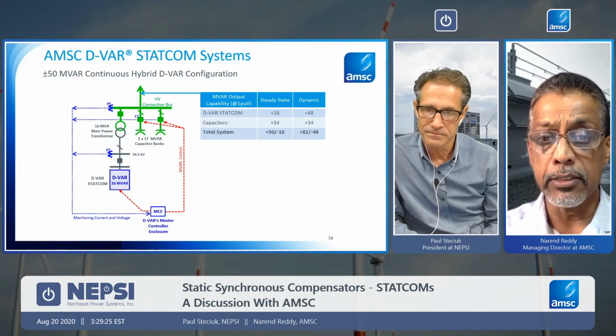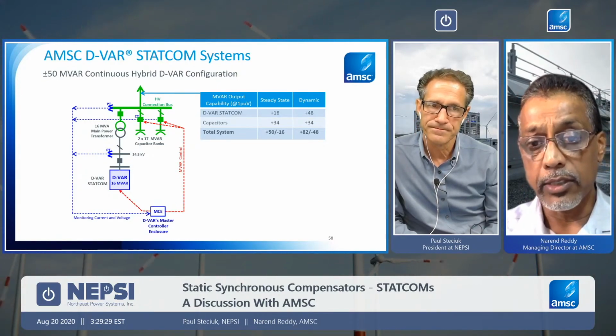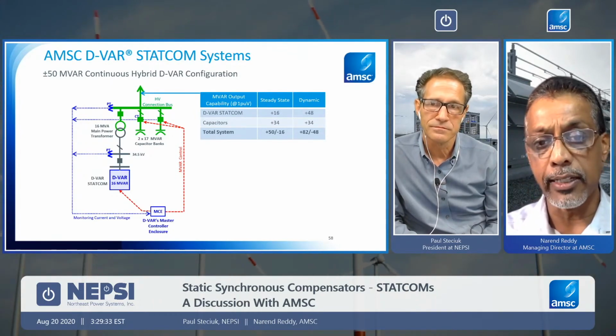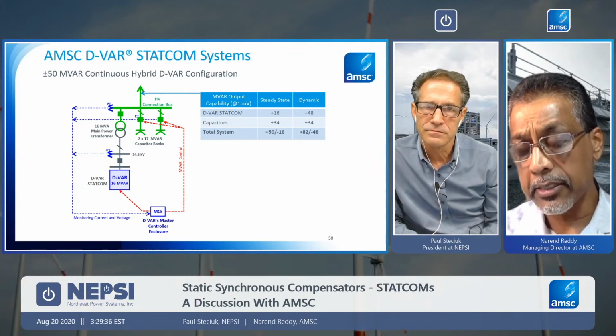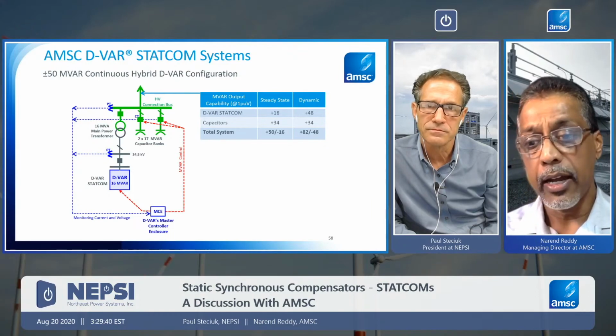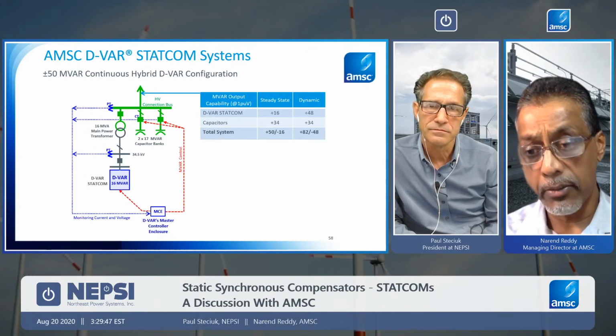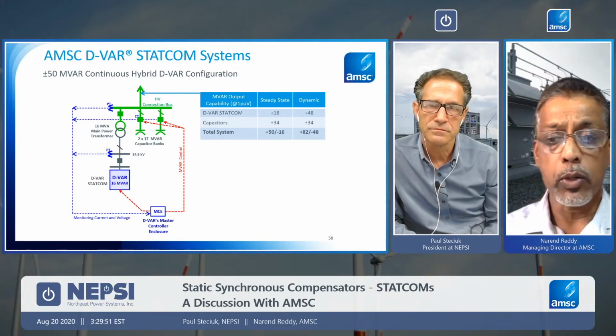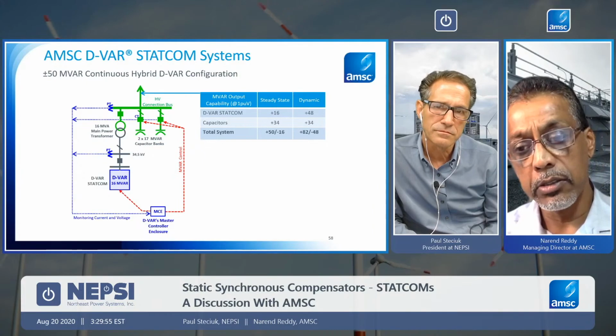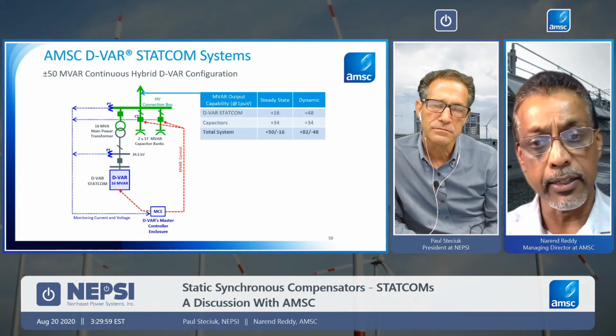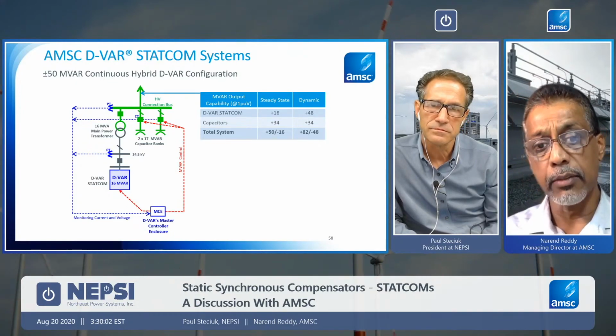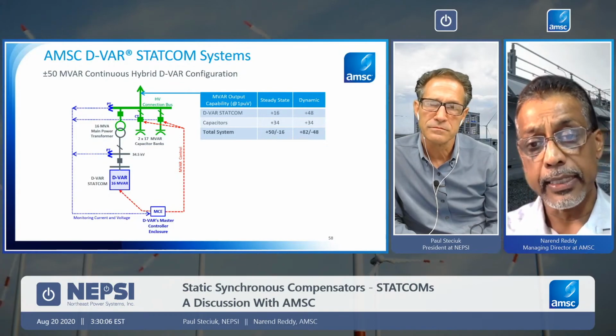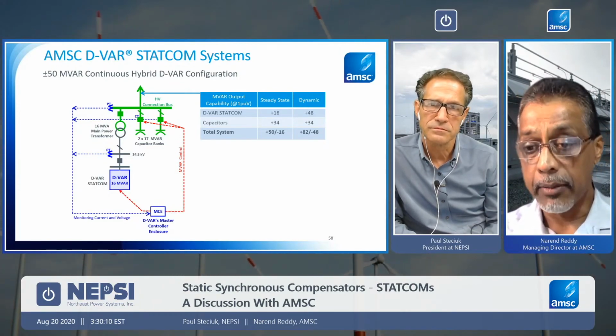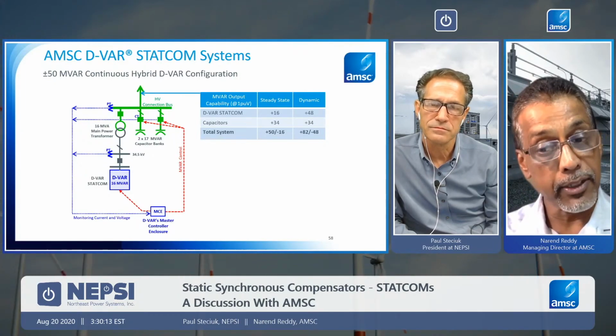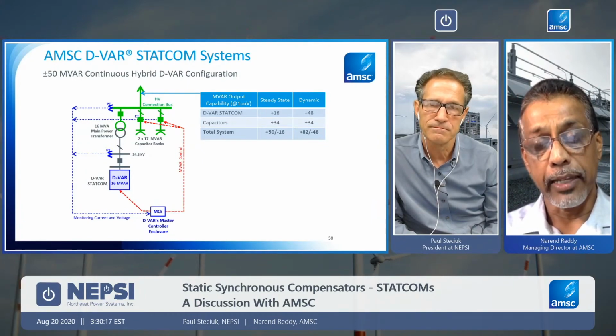Well, the way that we would approach that is to put in a STATCOM that's about a third of that rating. So a 16 megavar or 18 megavar STATCOM, in that range, would really meet the customer's 2-second or the full dynamic requirement, sag mitigation or transient response, all of that within that time frame, solve all the dynamic problem, and bring the voltages to normal ranges. But once the voltages are in the normal ranges, then we would actually use those cap banks, or reactors as it may be. But in this example, we are showing a 16 megavar DVAR with 2 by 17 megavar cap banks, really providing a 50 megavar dynamically variable system, but also providing a 50 megavar instantaneously variable system as well.